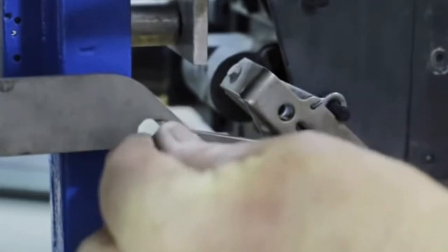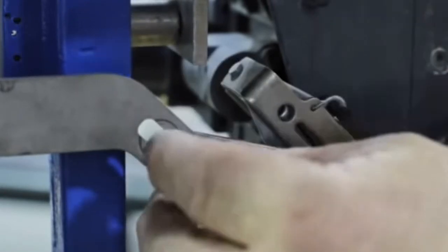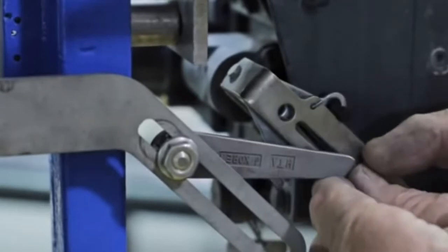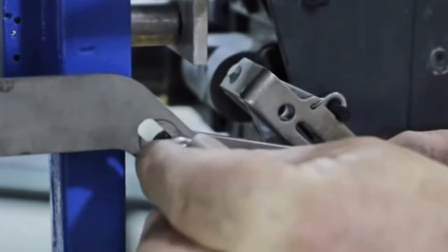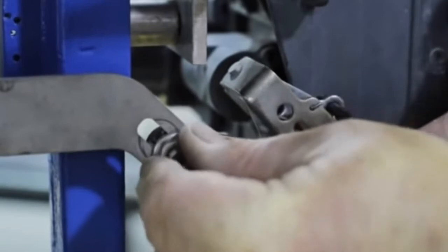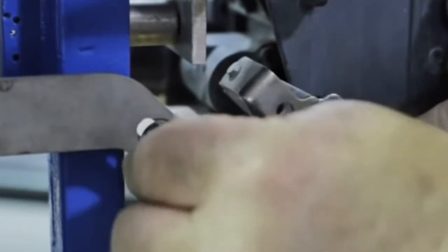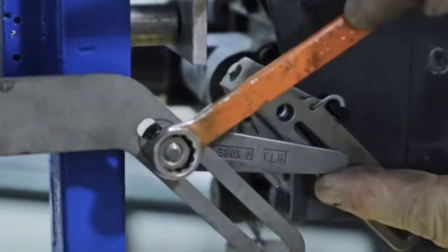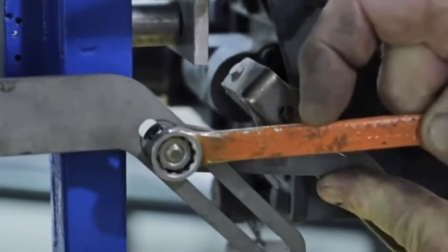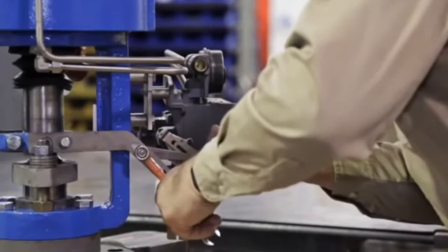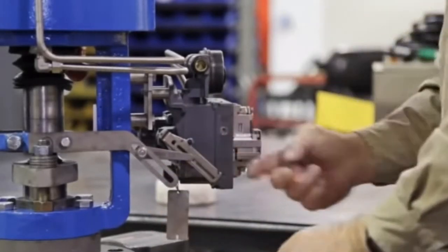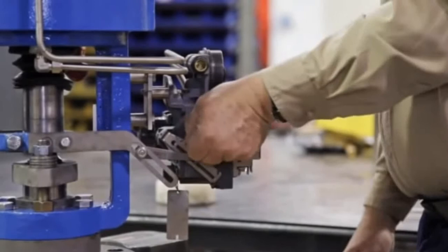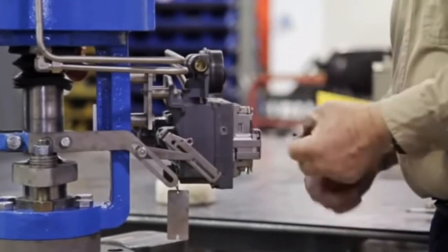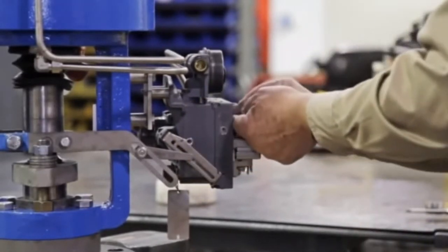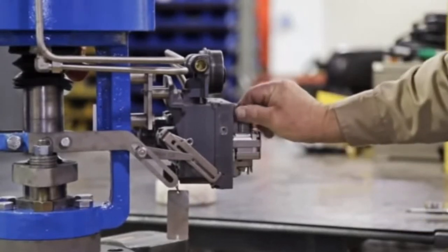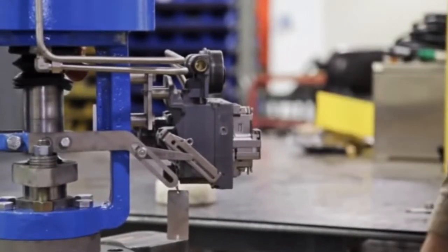Set the adjustment arm to align with the desired stroke length marked on the feedback arm. This valve has a 1.5 inch stroke, so we will align the arm pin with the corresponding mark. Tighten the adjustment arm. Remember to remove the alignment pin. We can now proceed with the calibration of the positioner.